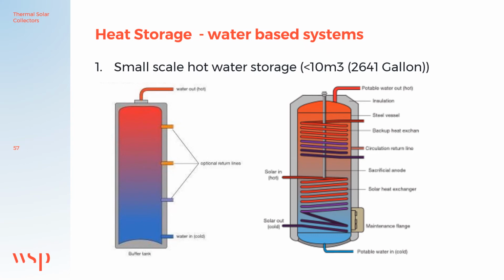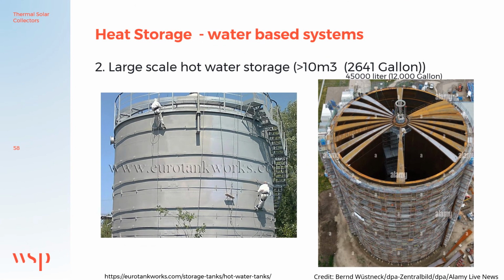These are examples of small-scale hot water storage tanks, which is typically less than 2,640 gallons. These are examples of large-scale hot water storage tank. The picture on the left is an example of a pre-manufactured, insulated, pressureless hot water storage tank assembled on site. The picture on the right is a 12,000 gallon insulated, pressureless hot water storage tank that's also under construction. The design temperature of the water inside the tank is 208 degrees Fahrenheit, which serves as a heat source for a heating water for a district heating plant.